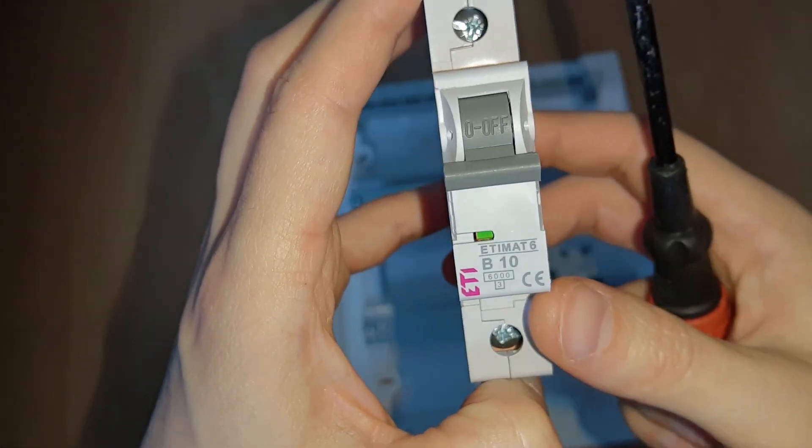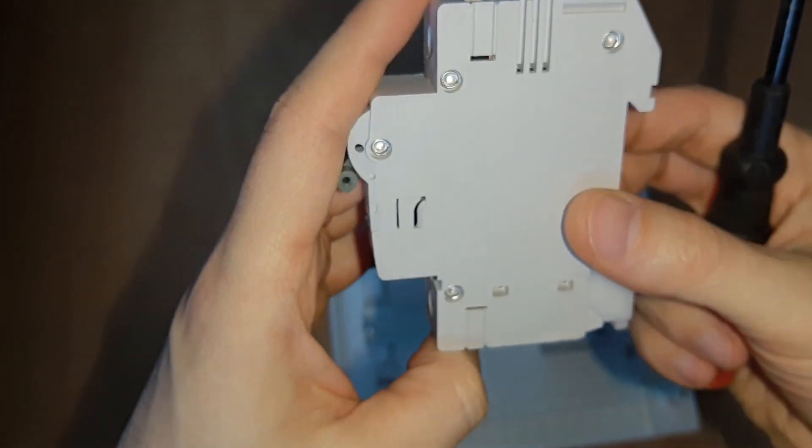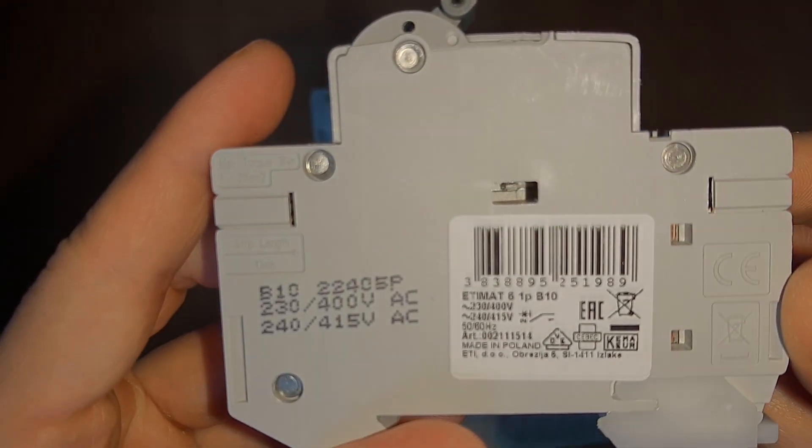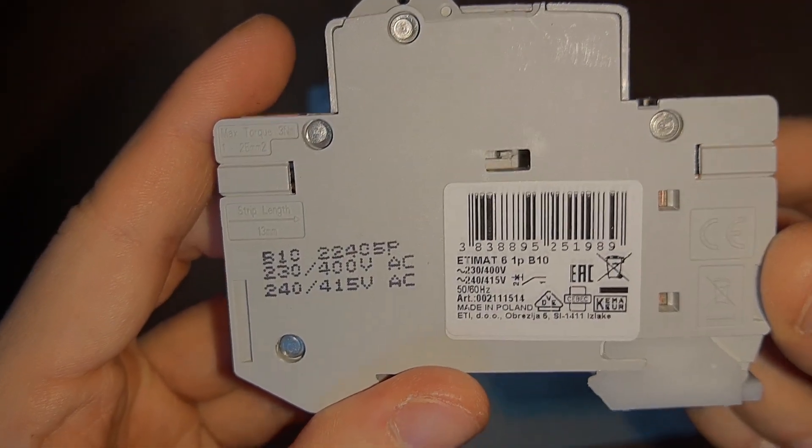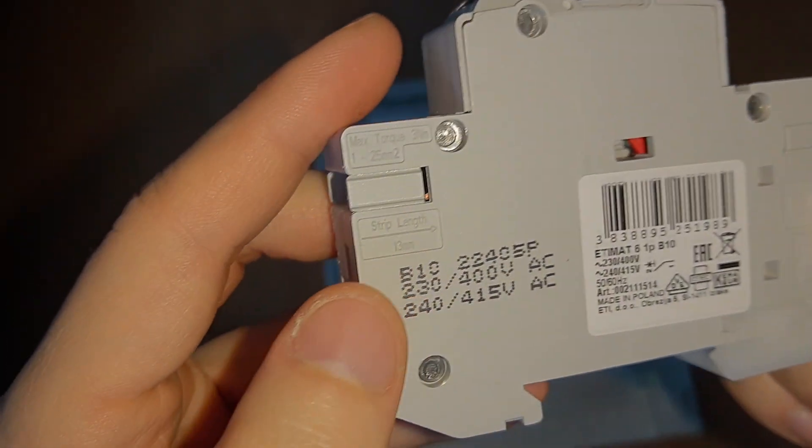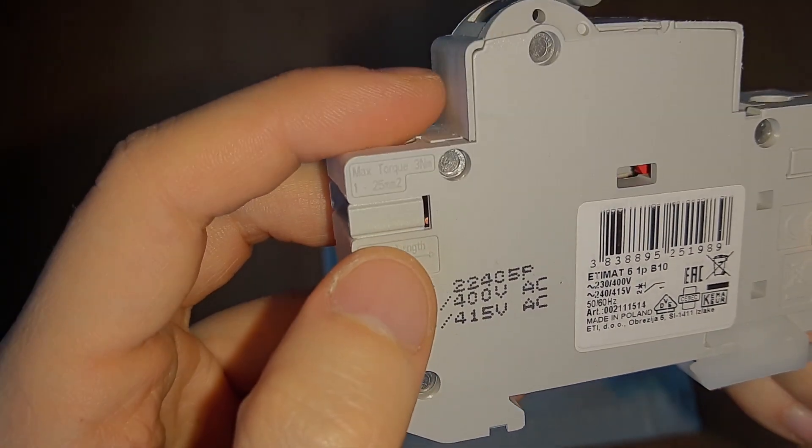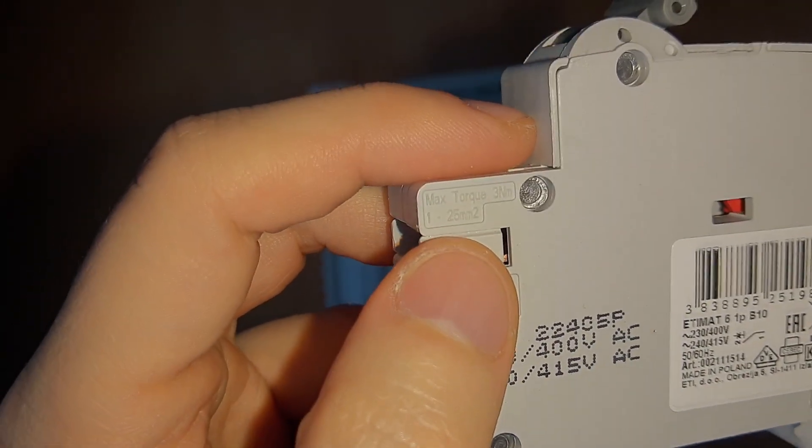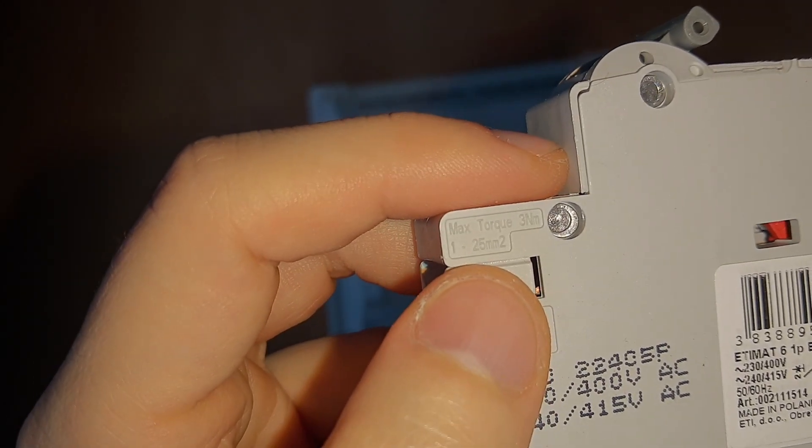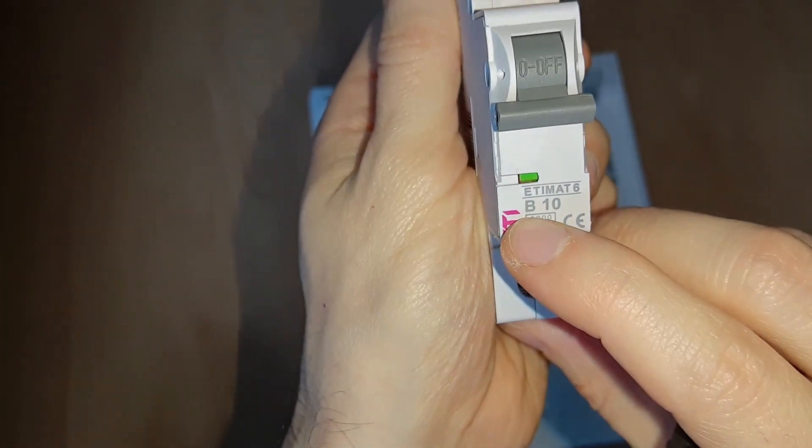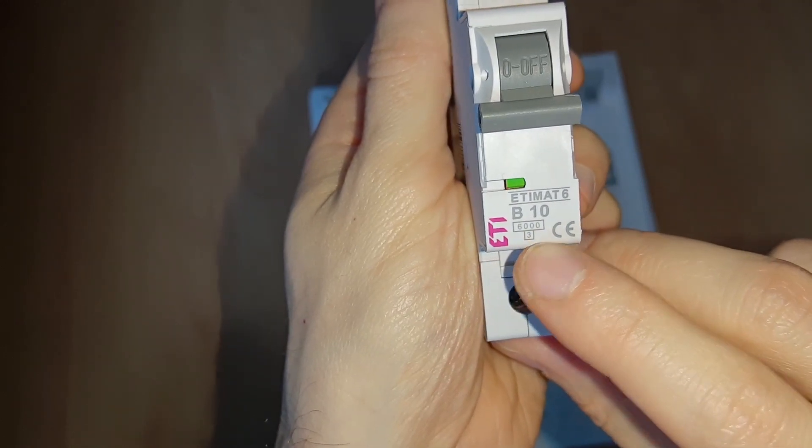Okay, so normal MCBs, micro breakers. You have here strip length 13 millimeters, wire gauge 1 to 25 square millimeters, and torque up to 3 newton meters. This is B type at 6 kiloamperes.